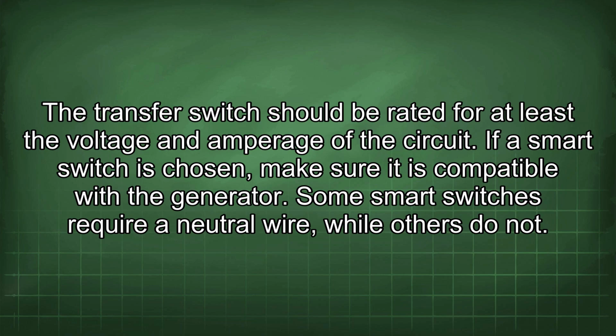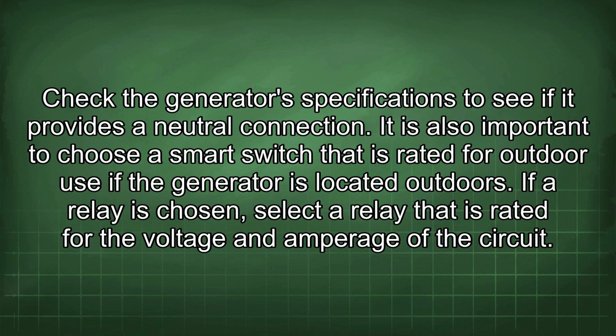If a smart switch is chosen, make sure it is compatible with the generator. Some smart switches require a neutral wire, while others do not. Check the generator's specifications to see if it provides a neutral connection. It is also important to choose a smart switch that is rated for outdoor use if the generator is located outdoors. If a relay is chosen, select a relay that is rated for the voltage and amperage of the circuit.